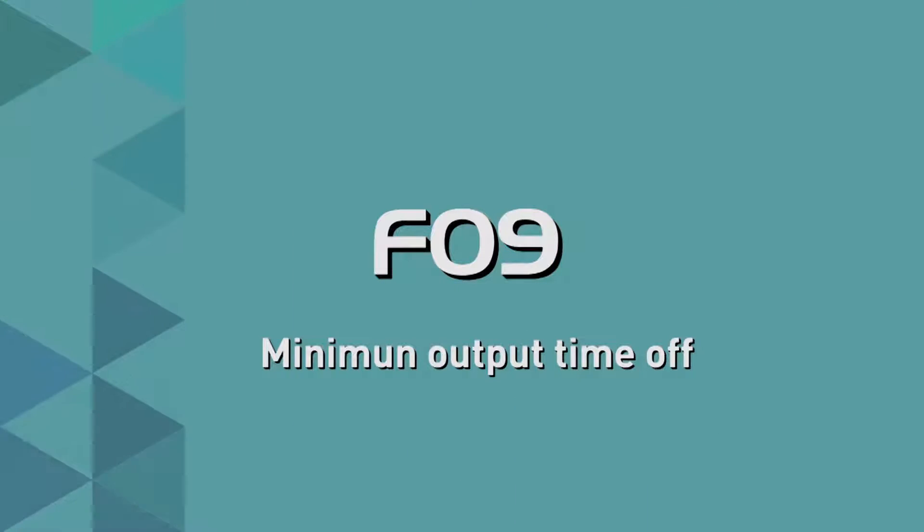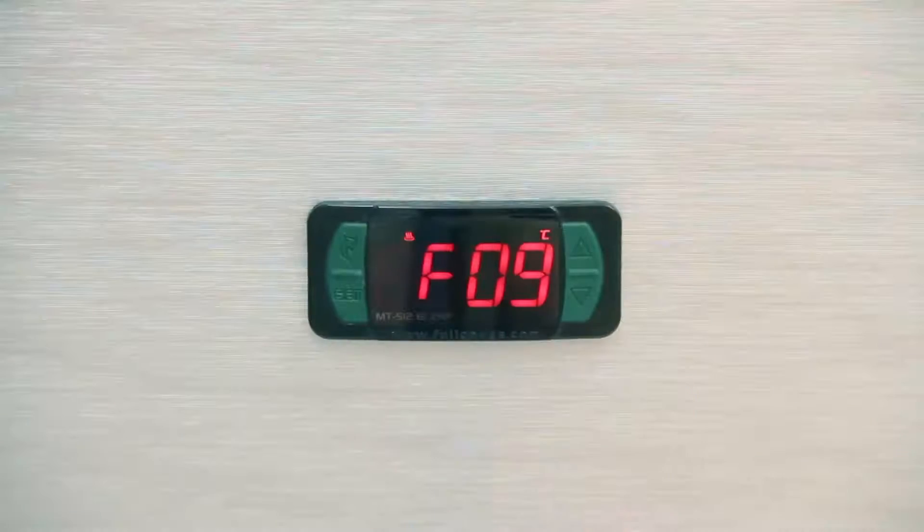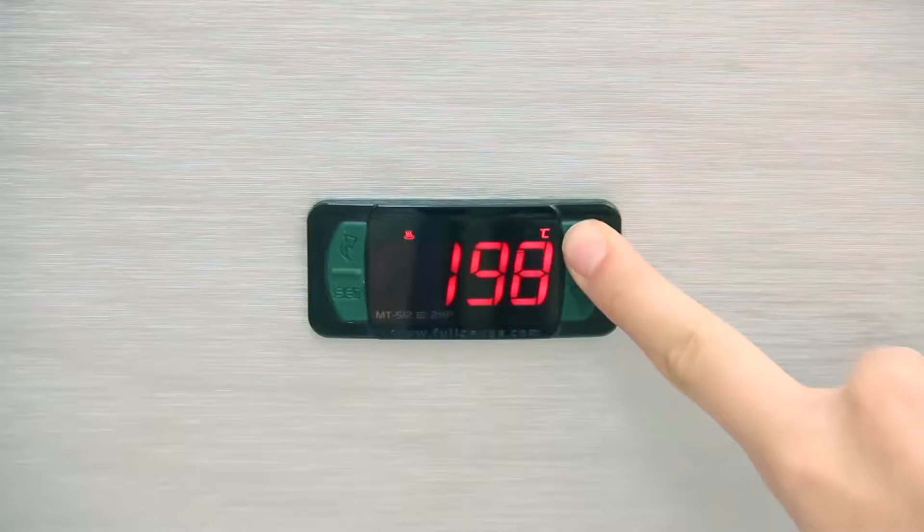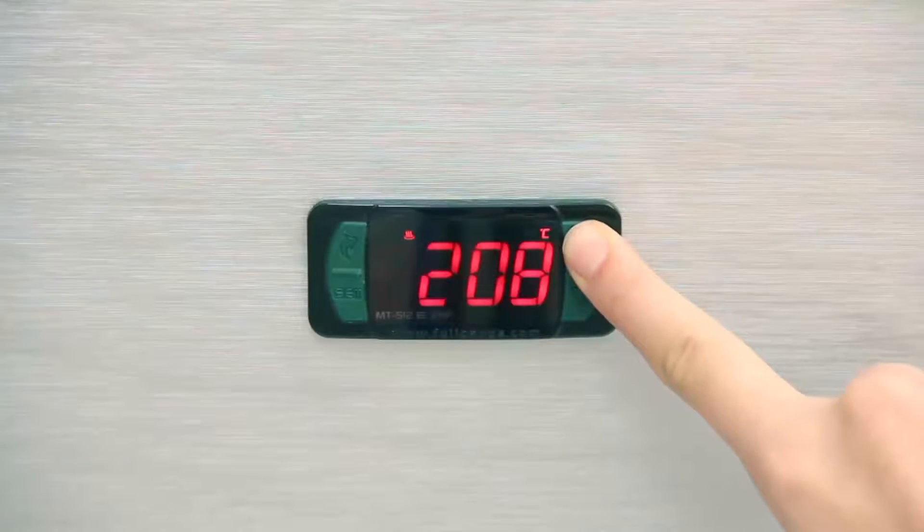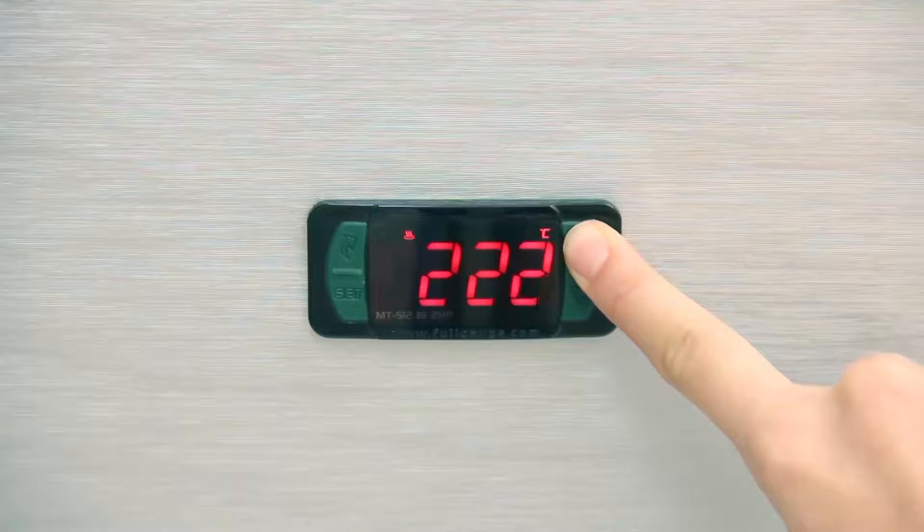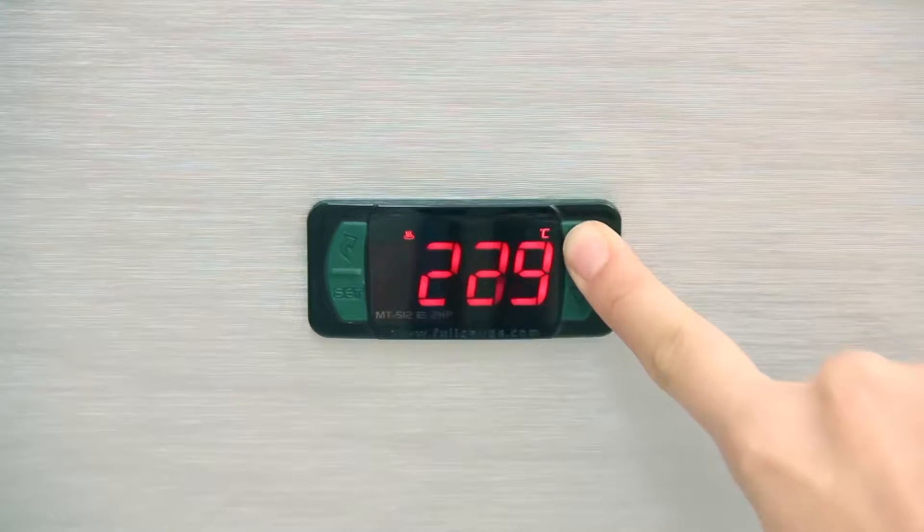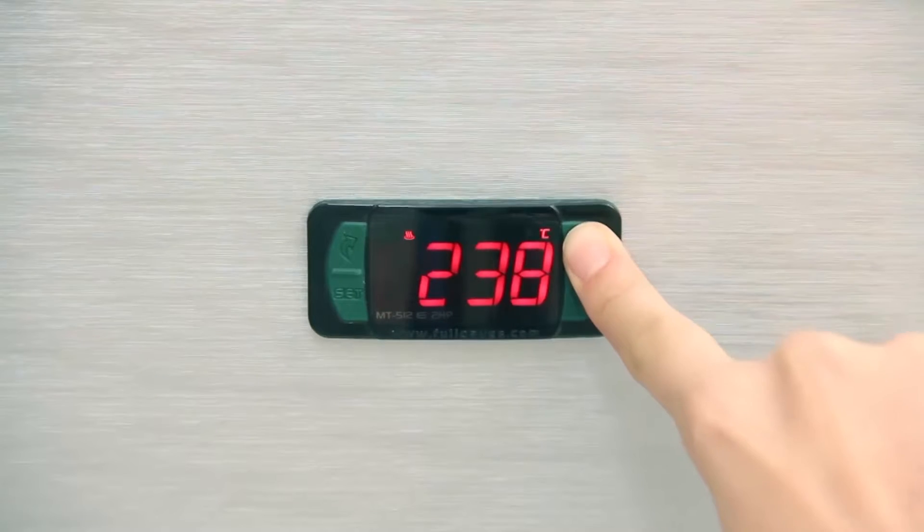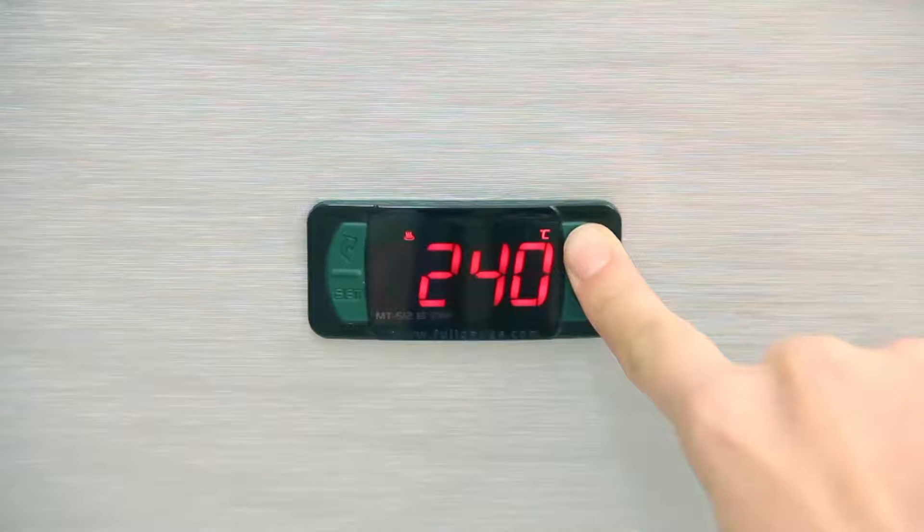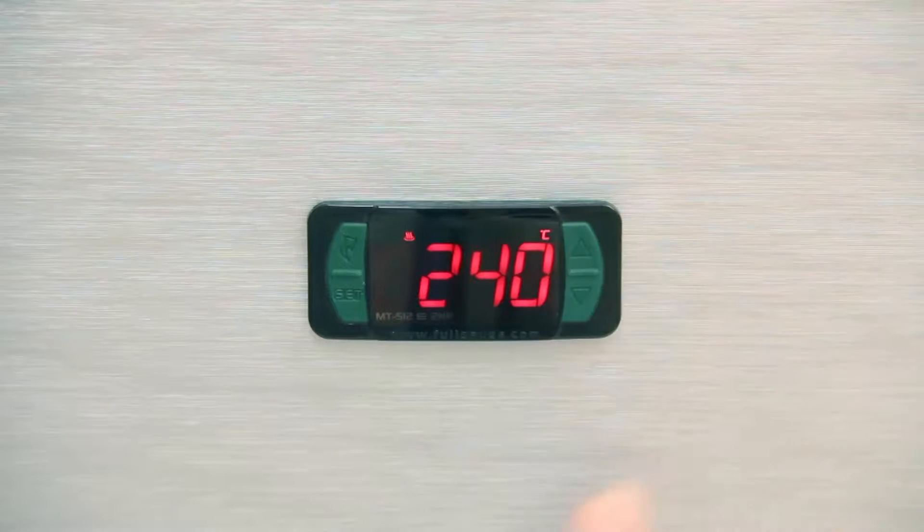F09, Minimum Output Off Time. Similar to the previous parameter, this determines the minimum relay off time since the last start. Select No, so as not to adopt a minimum time, or provide a value between 1 and 999 seconds. In the examples, we chose 240 seconds for both applications.